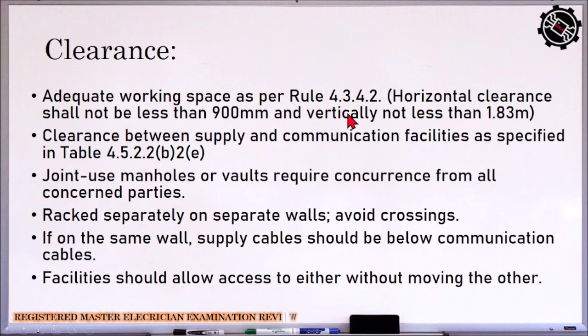Clearance between supply and communication facilities is specified in table 4.5.2.2b2e. We will have a copy of this table later. Joint use manholes or vaults require concurrence from all concerned parties. So if our manholes are to be used by two or more companies, they should have an agreement that they can both use the manholes. Rack separately on separate walls and avoid crossing. The cables that can be accessed in the manhole should be separated properly and should not cross each other in our manhole.